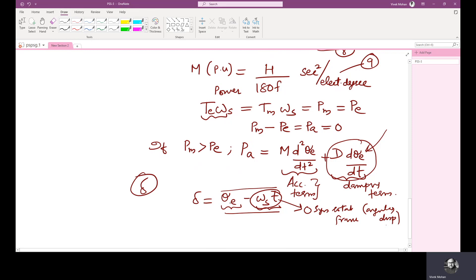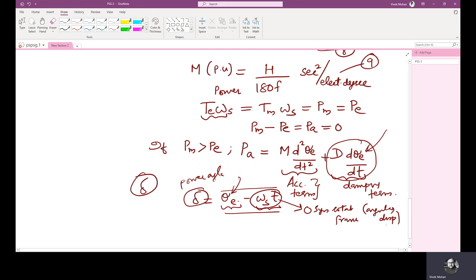Theta E is the physical angular position of the rotor. If we take the relative angle between both, we get the power angle del. Now, when will del vary? If there is a disturbance from the generation side or the demand side, the physical angular position of the rotor with respect to the position of the synchronously rotating frame will change. Otherwise, at steady state, both are locked. Of course there is an angle, but that angle is constant. This angle will change whenever there is a disturbance.